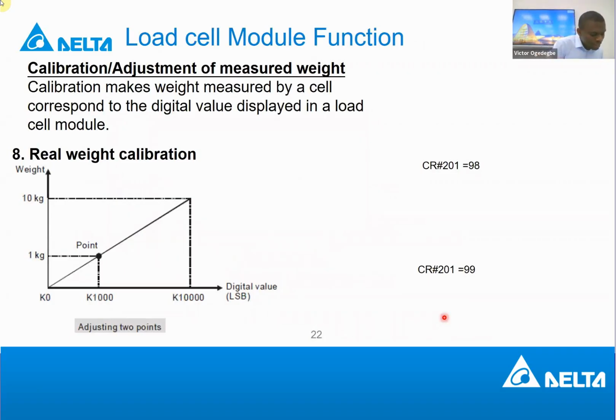The last function, before we call it a day, we took quite some time, I was thinking it would be shorter than this, is calibration or adjustment of measured weights. So what is the essence of calibration? Calibration makes the weight measured by a sensor correspond to the digital value displayed in the load cell module. Your load sensor is measuring 1 kg, and that 1 kg can represent, for example, a digital value of 1,000 in your module. So if you see 1,000, you can tell your module to do what has to be done. For that to be possible, you need to calibrate the module so that if it reads 1 kg, it will give you 1,000.